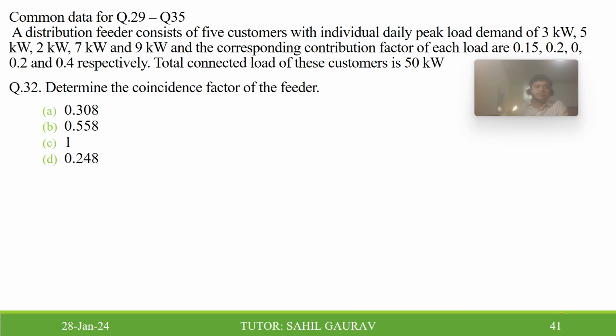Now the next problem is that you have to find the coincidence factor of the feeder. The coincidence factor is quite easy. It is the reciprocal of the diversity factor. So 1 divided by DF, and the diversity factor we have calculated, that is 4.031. So it will give you 0.248. So the correct answer is D.